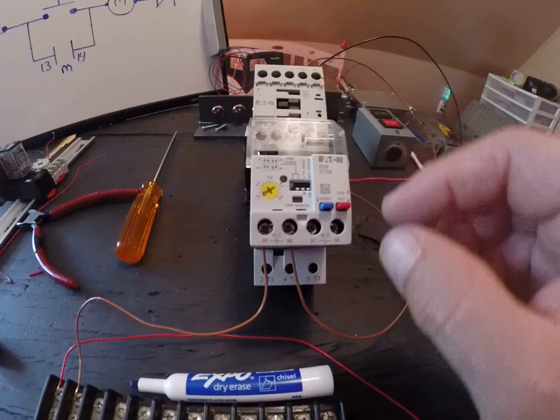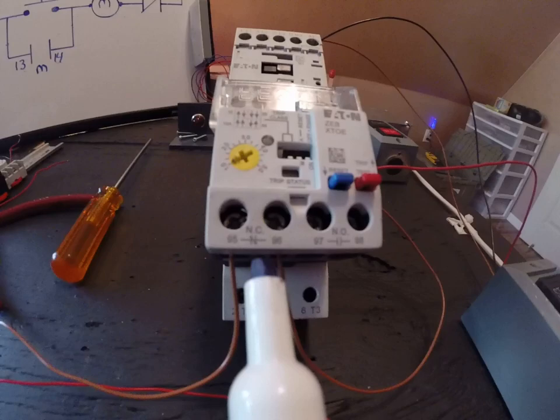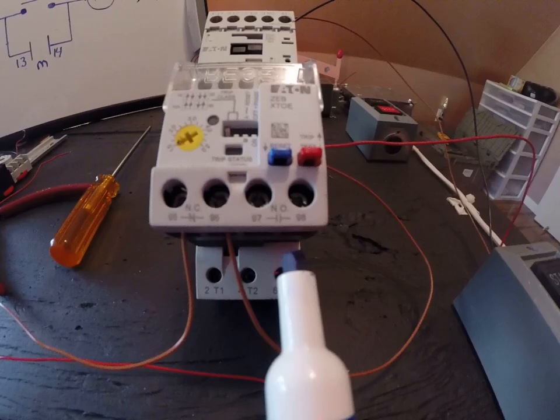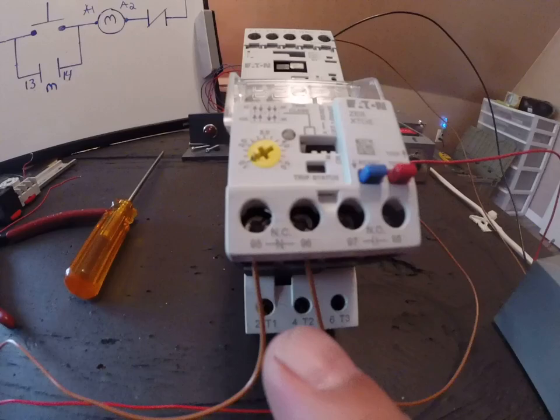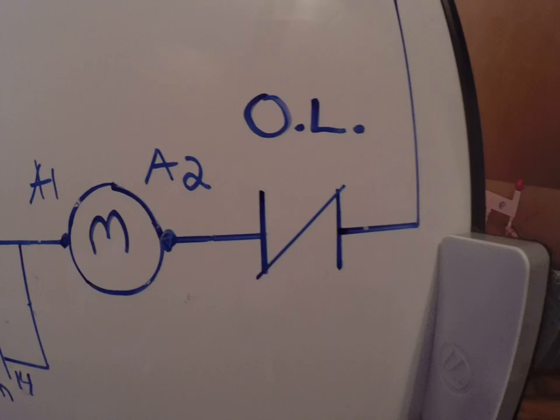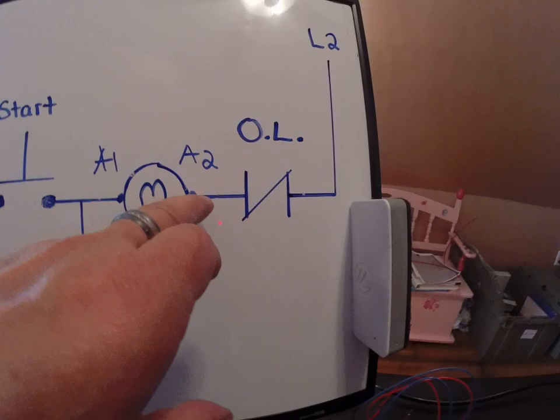So in other words, if this motor trips on overload, what's going to happen is this normally closed contact is going to open, and this normally open contact is going to close. So that's why I have wires tied on to the normally closed. So remember, in our drawings, our overloads are normally closed.